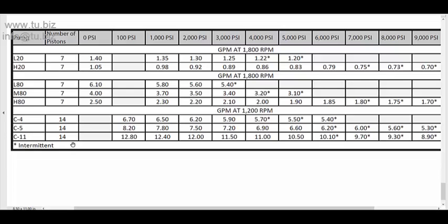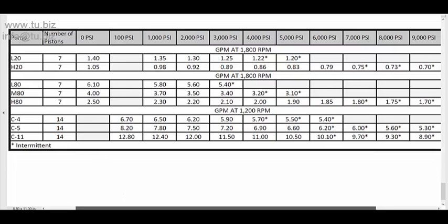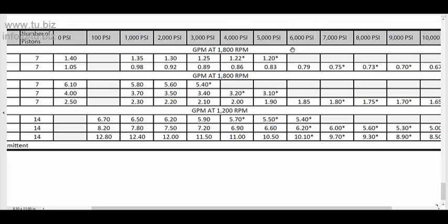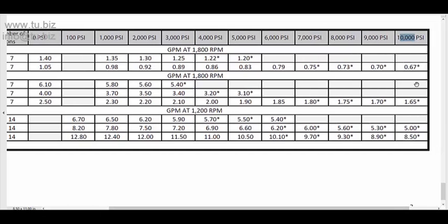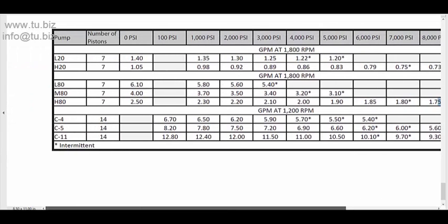Now if we look over here in this section, we have the pressure ratings and you see it comes up to 10,000 PSI. But you have to be careful because the 10,000 PSI up to the very end, that's just for intermittent. You have to watch the little star next to the number. That means the pump is intermittent only. I would not run it more than five seconds. So it's only for a few seconds that you're going to run it at that pressure.